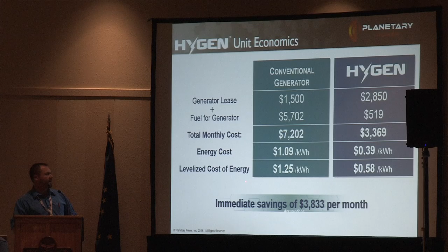A cost breakdown on this, a lot of folks we deal with are really concerned with the capital costs, so we bring that on a monthly or lease basis. What we see is a cost of generation at about $4.40 a gallon, we're seeing on some of those conventional diesel generators as much as $1.09 per kilowatt hour in a variable load situation, where we can be very fixed at 39 cents per kilowatt hour with a levelized cost of energy at 58 cents per kilowatt hour.